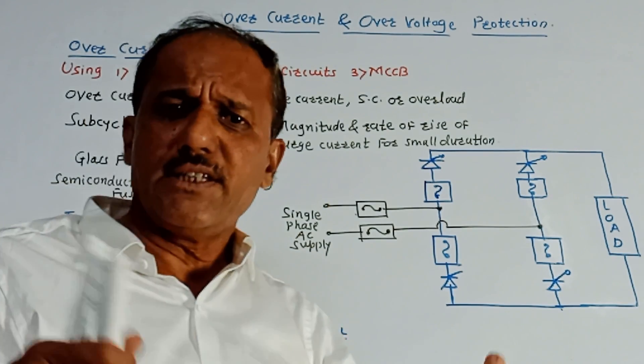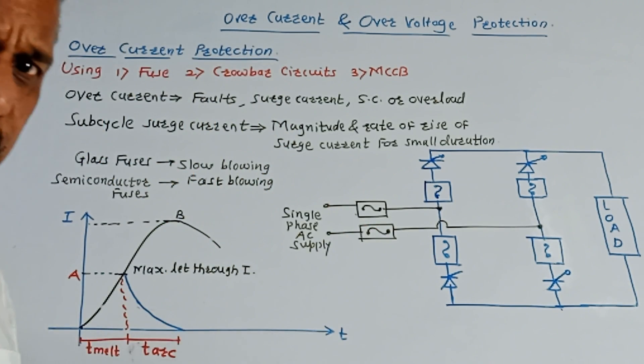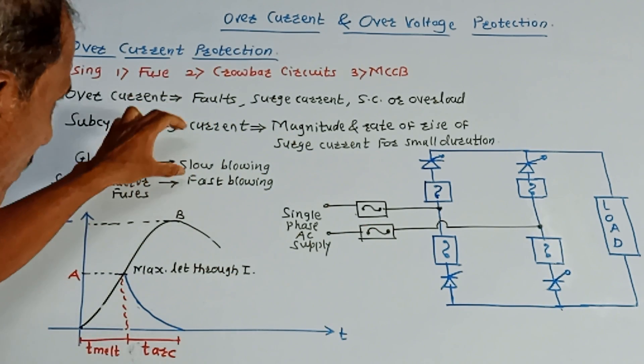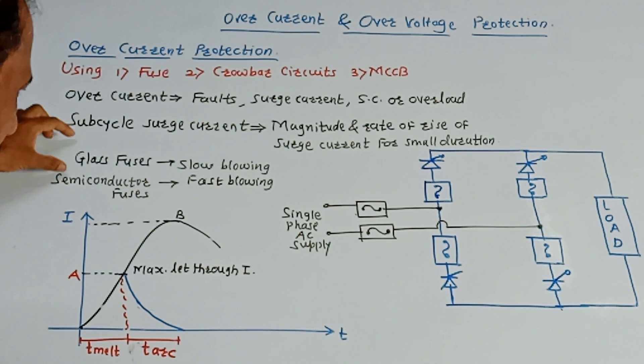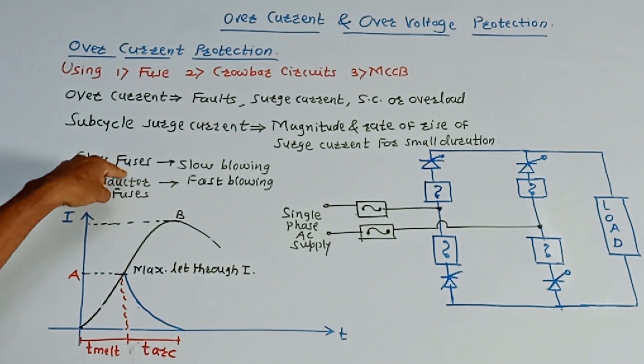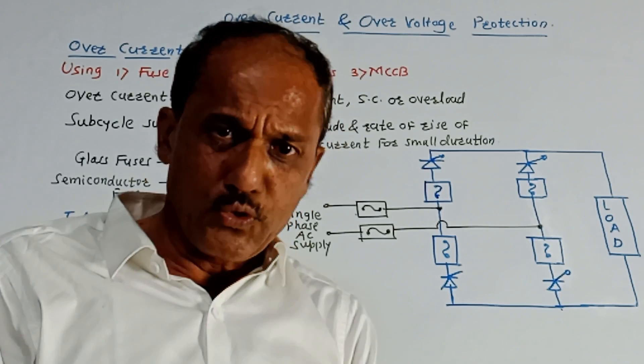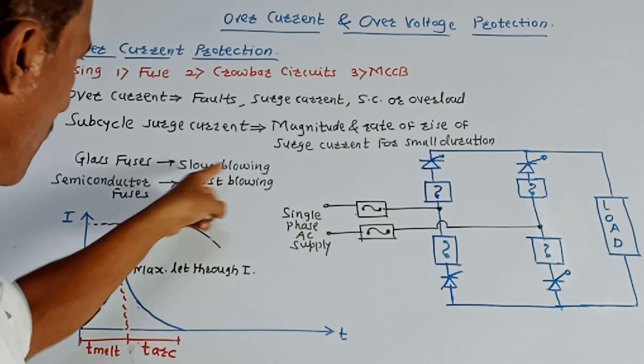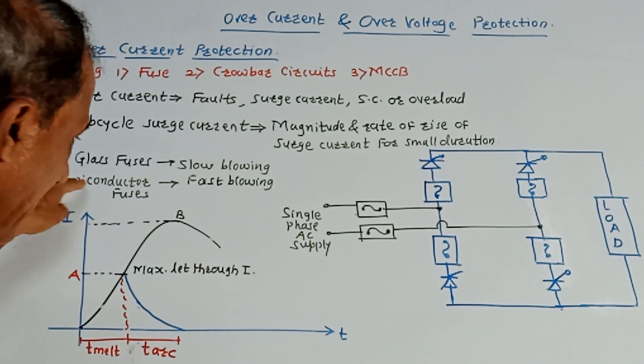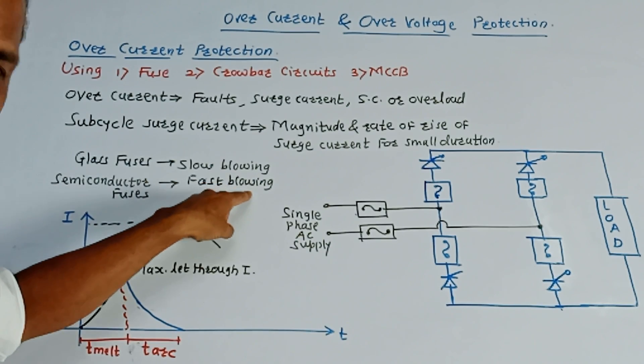To protect the power devices, two types of fuses are used. We are talking about the first technique, that is using a fuse for the protection purpose. There are two types of fuses: one is glass fuse and another is semiconductor fuse. In case of a glass fuse, it is not preferred for power electronics devices because it is slow blowing. Whereas these semiconductor fuses are preferred because of the fast blowing action.